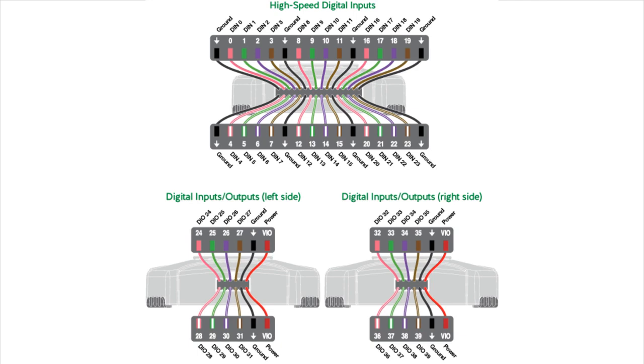On the front, there's a high-speed port, and you can see data and ground interleaved. You can use this port for up to 800 or 400 mega samples per second, but you'll need the high-speed add-on. That's why there are two products on DigiKey — one has the high-speed port adapter and one doesn't. On the side, there are two lower-speed eight-port connections, two power, two grounds, and eight pins on either side — so a lot of I/O.